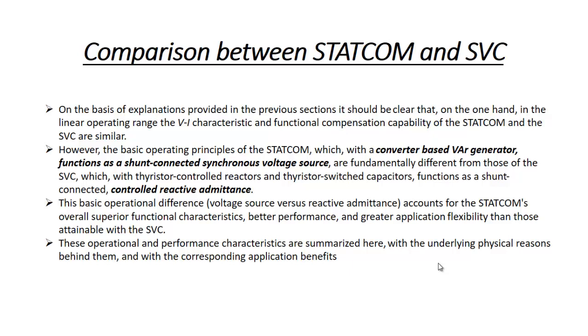The operating principle of the STATCOM, which is based on the converter-based VAr generator, functions as a shunt-connected synchronous voltage source. It draws a current which is in quadrature to the generated voltage. This is definitely different from the SVC, which is composed of thyristor-controlled reactors and thyristor-switched capacitors that function as shunt-connected controlled reactive admittances. In the STATCOM we change the voltage source magnitude and keep the current angle always in quadrature. This basic operational difference — voltage source versus reactive admittance — accounts for the STATCOM's better performance and greater application flexibility than the SVC.